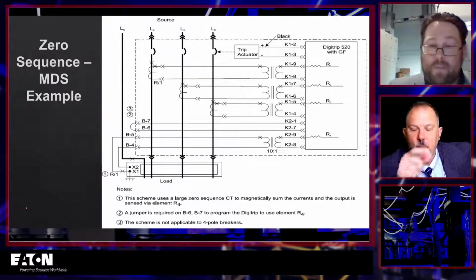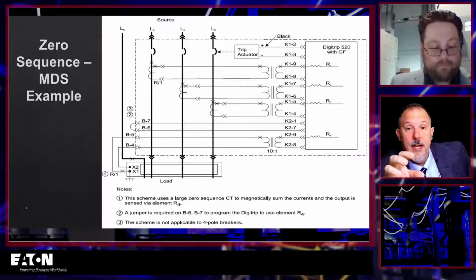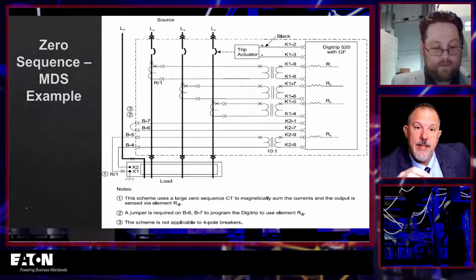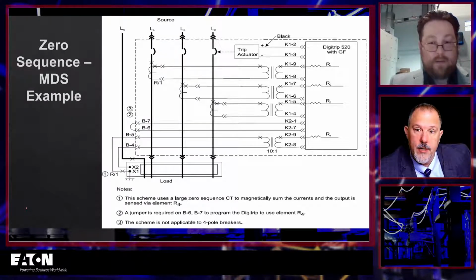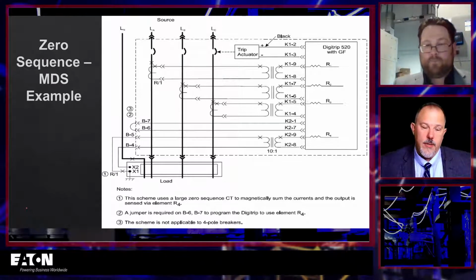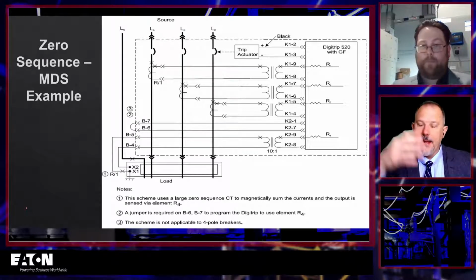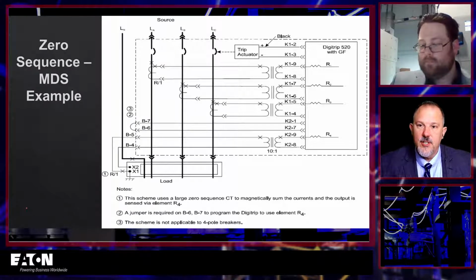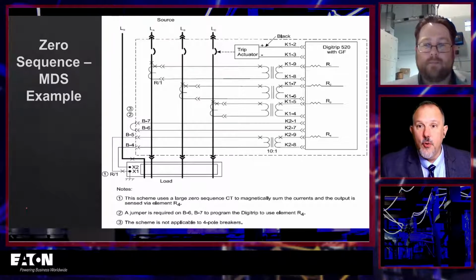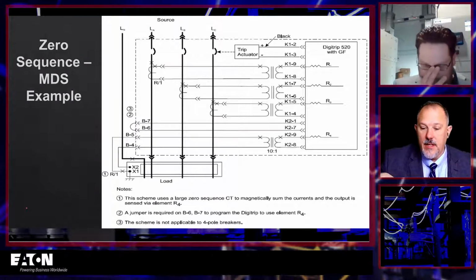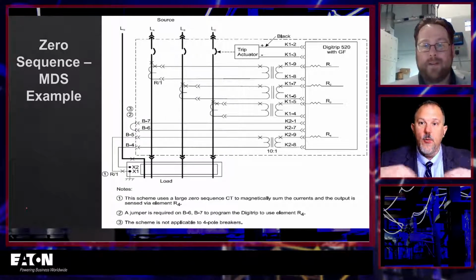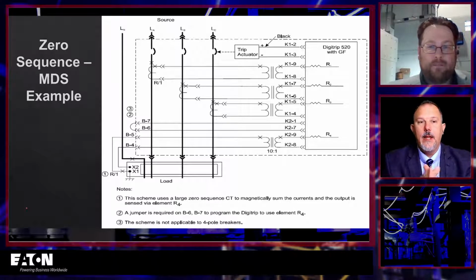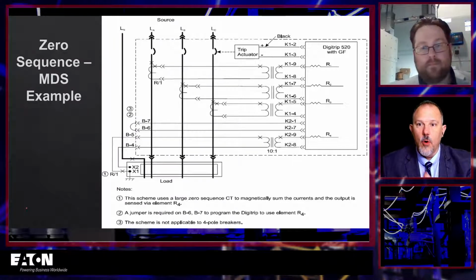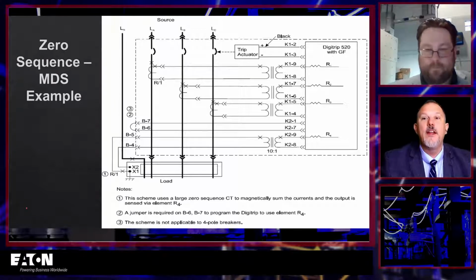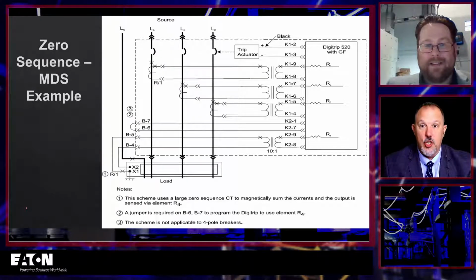I had a question one time from a customer of ours who had one of our larger breakers on a circuit that had very, very low current. So it was a very large breaker. It had very low current. And everything was sized correctly. But his concern was that typically there's not enough current drawing, to your point, that the trip unit is like awake, right? Because we're getting the power off of that current that's flowing through there. And his question was, will your breaker actually function and work and trip? And the response to that was that when you have a fault, you'll have enough fault current that it will drive that trip unit to open and do its job.